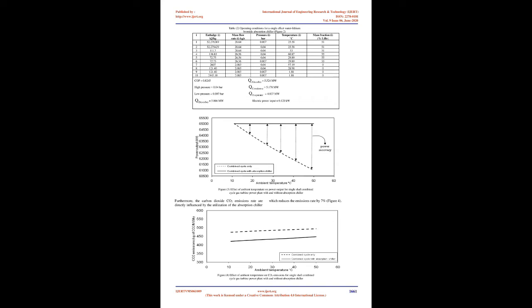3.1 The power plant behavior at ISO conditions. The first set of tests has been performed at ISO conditions: ambient temperature 15 degrees Celsius, relative humidity 60%, and atmospheric pressure 1.01325 bar, with seawater temperature at 25 degrees Celsius. The power plant at this condition was able to produce 67 MW power output with 1375 RT cooling effect for compressor inlet air and another 1375 RT cooling effect for air conditioning and food storage requirements.